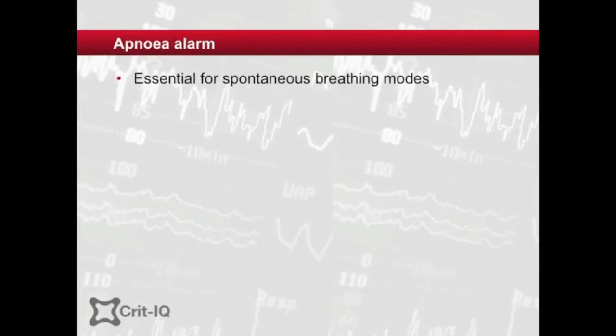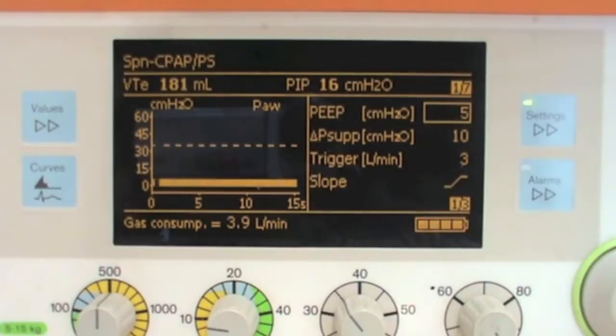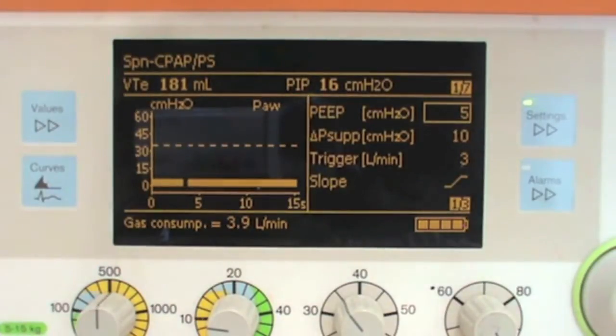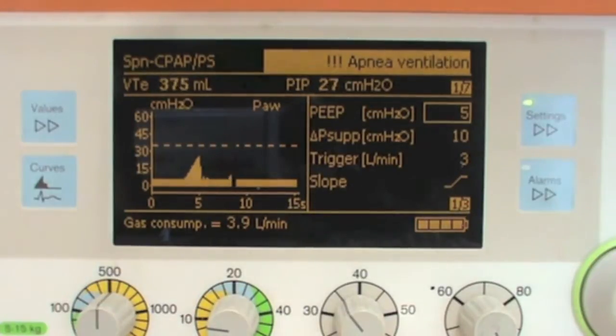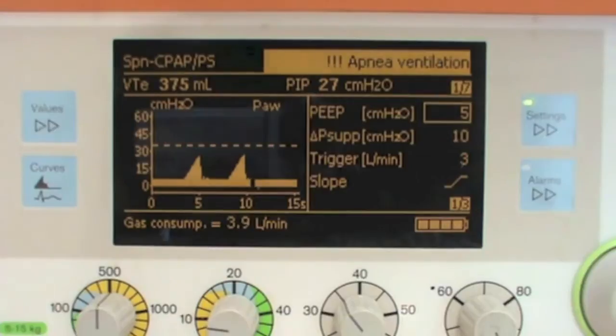The apnoea alarm is important in modes where initiation of the breath is entirely triggered by the patient, for example pressure support modes. In these circumstances, if the patient becomes apnoeic, no ventilation will occur and the patient would rapidly deteriorate. Most ventilators, in addition to alarming, will cycle into a mandatory backup rate when this alarm is triggered.